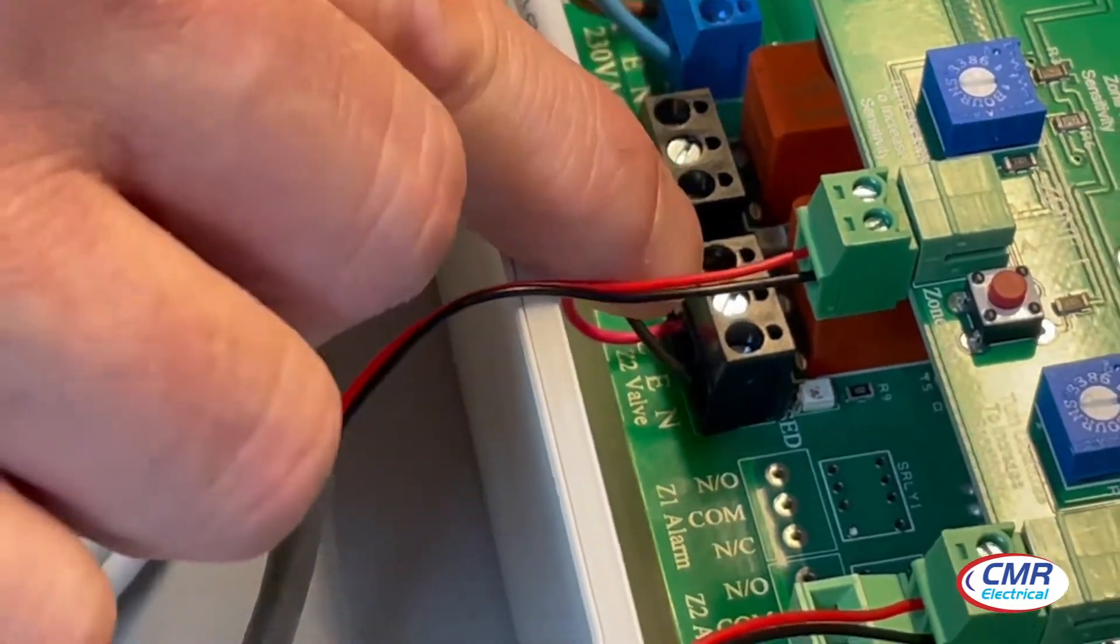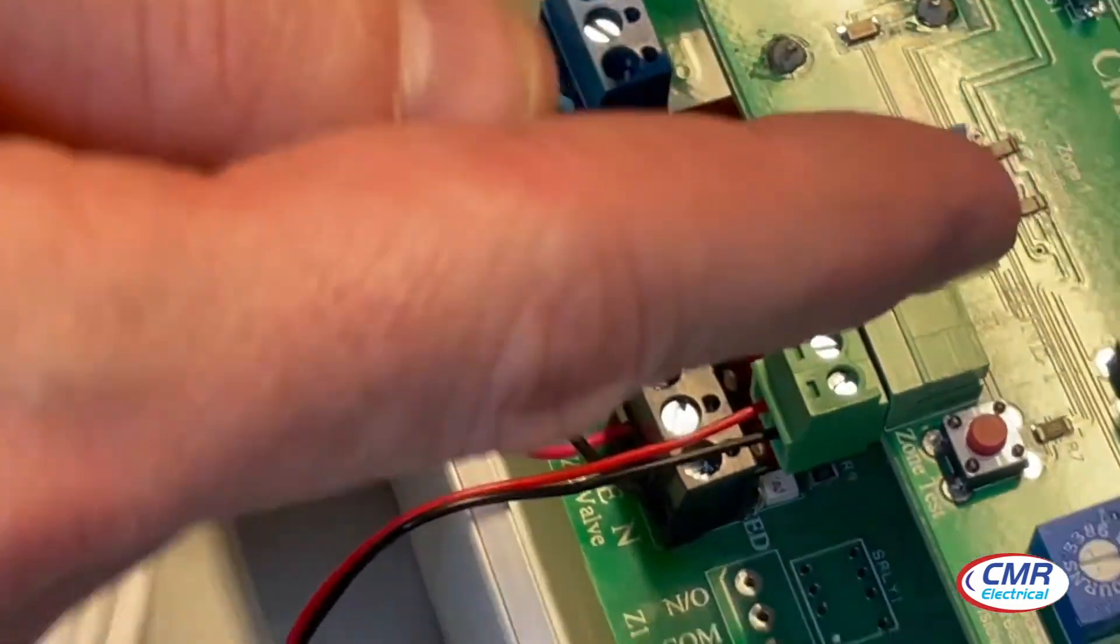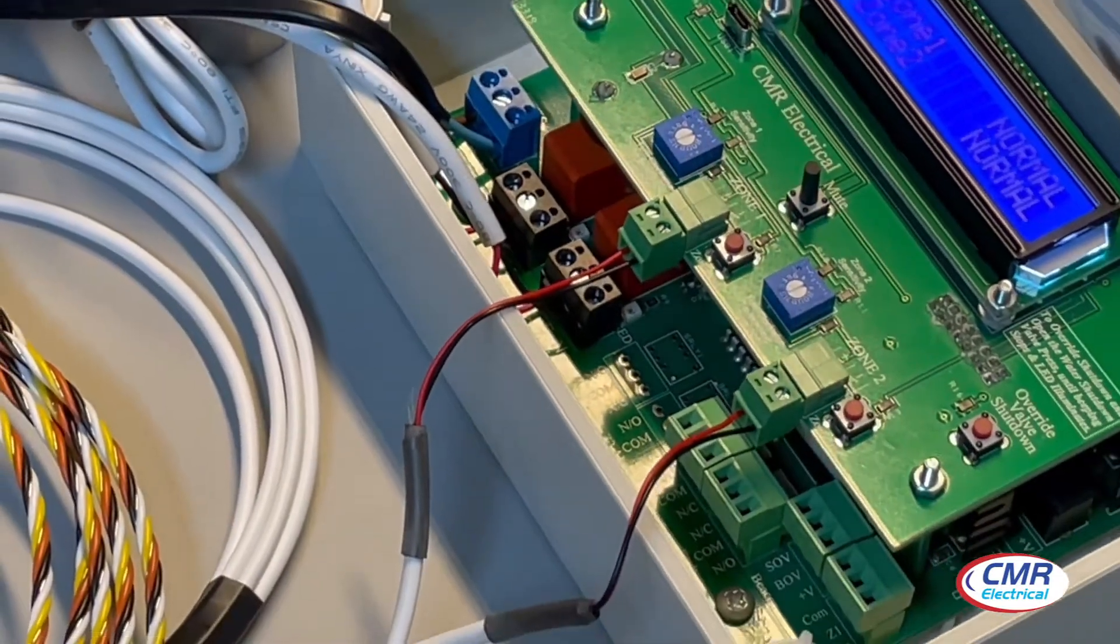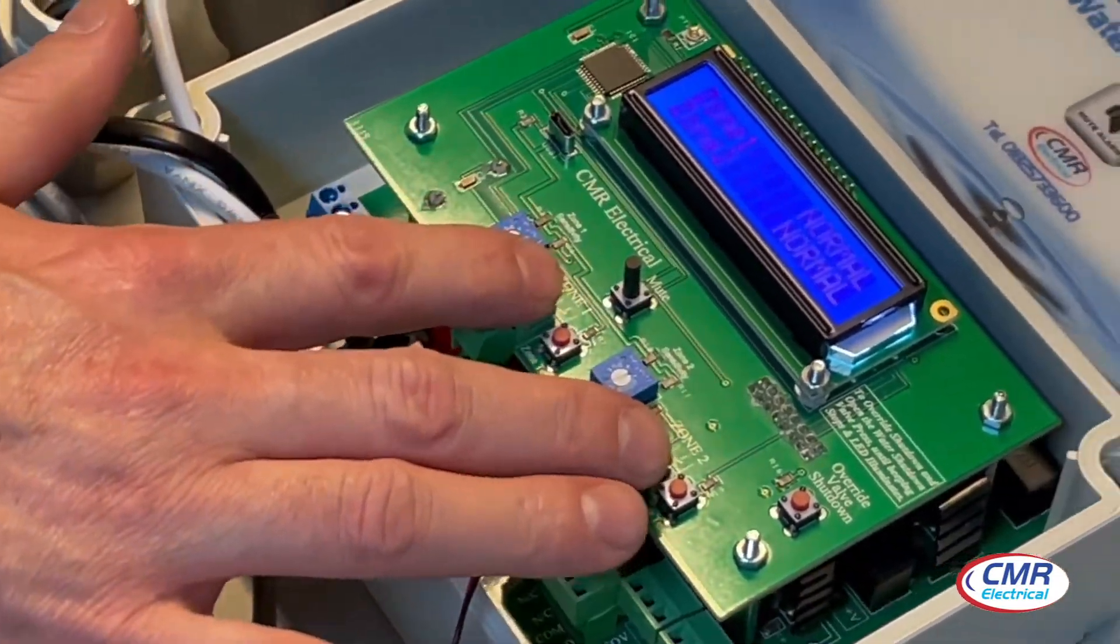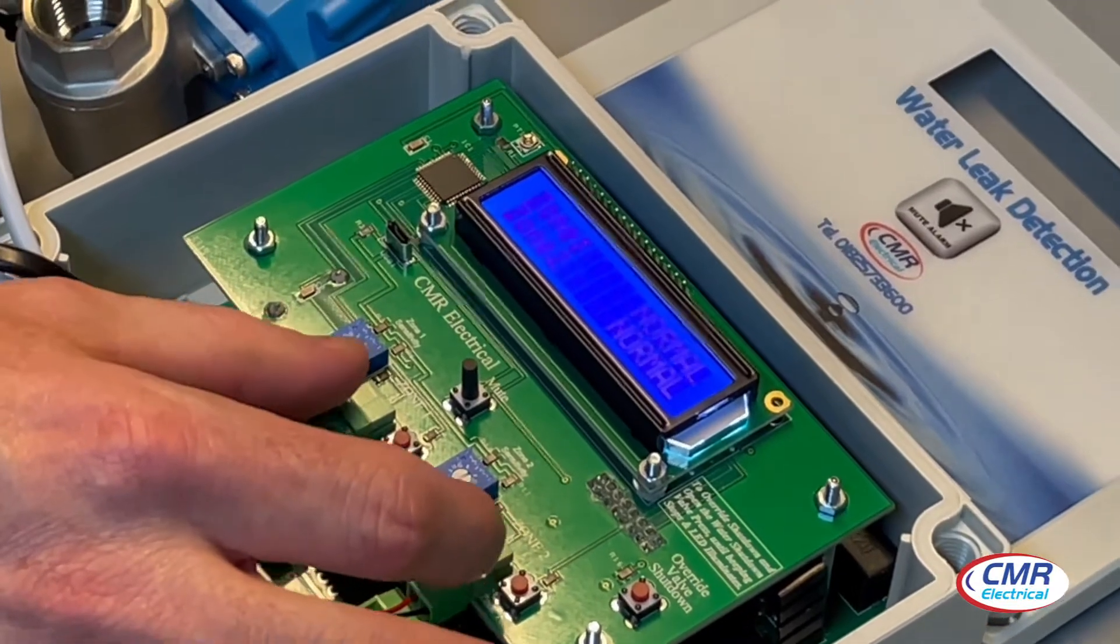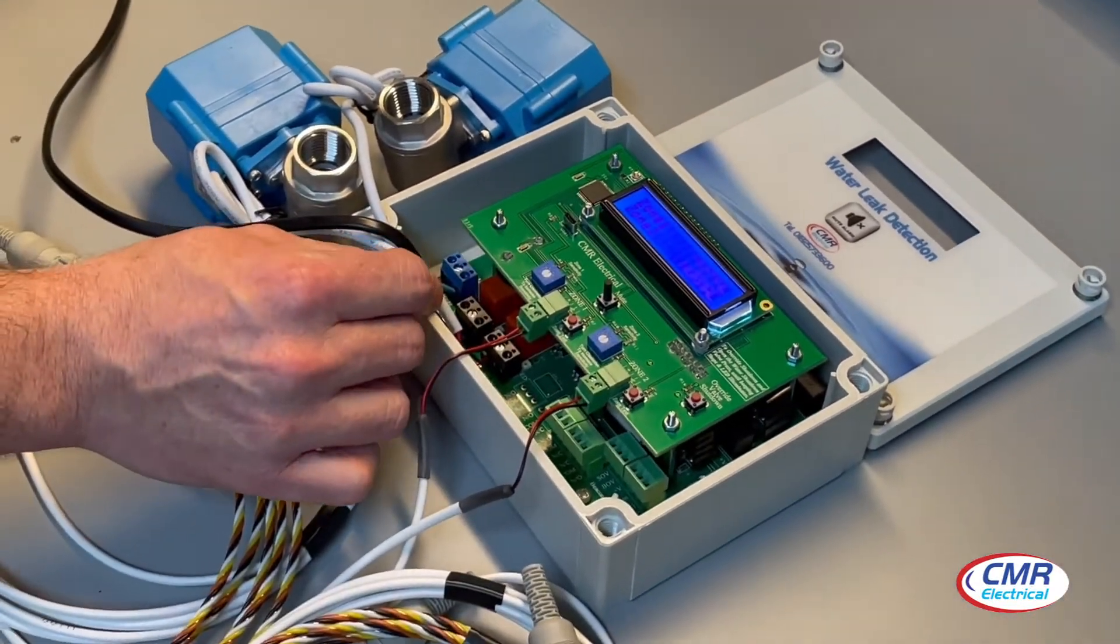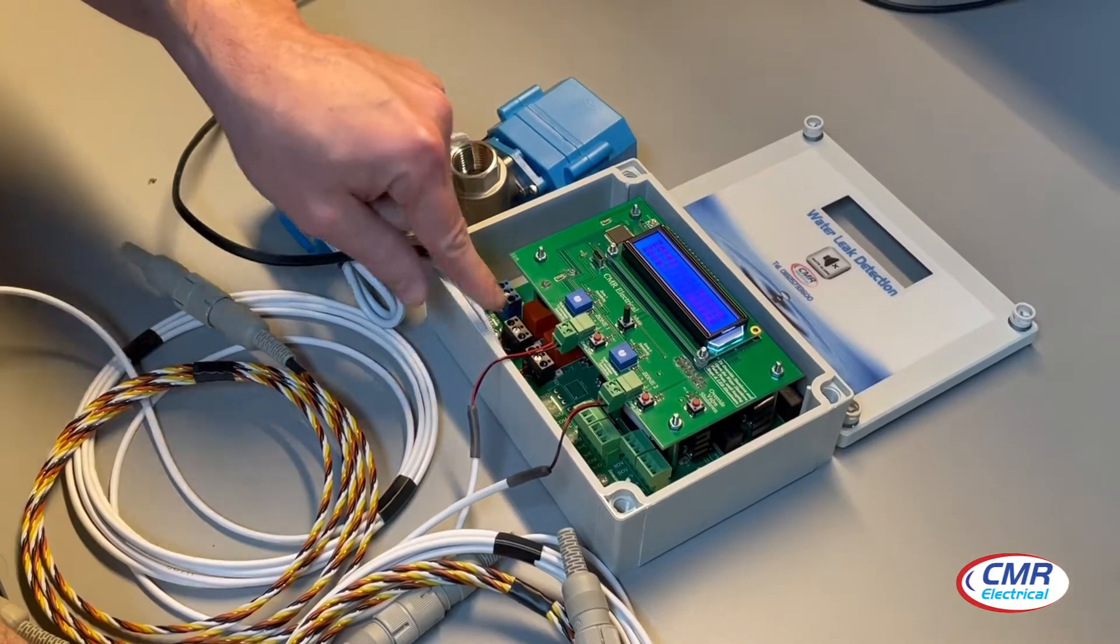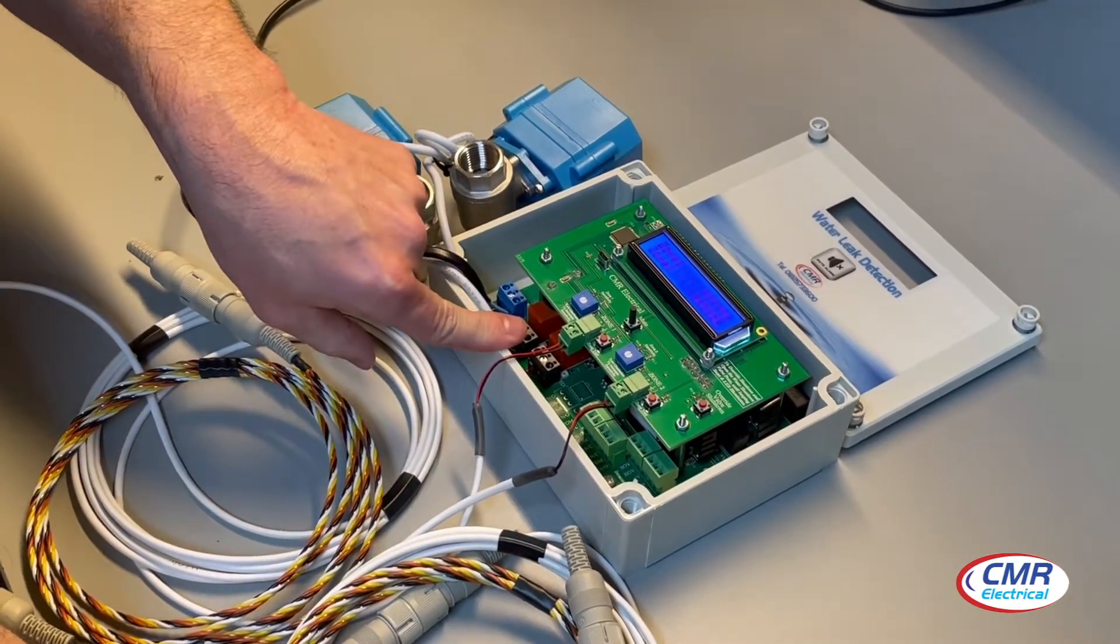Your two terminals here will be individual zone valve control per zone, or you can have common valve control, which means if you have a two-zone system, any of those two zones going into alarm will turn off a valve. As you can see down there, you've got your live, earth, and neutral. Exactly the same for the second zone.